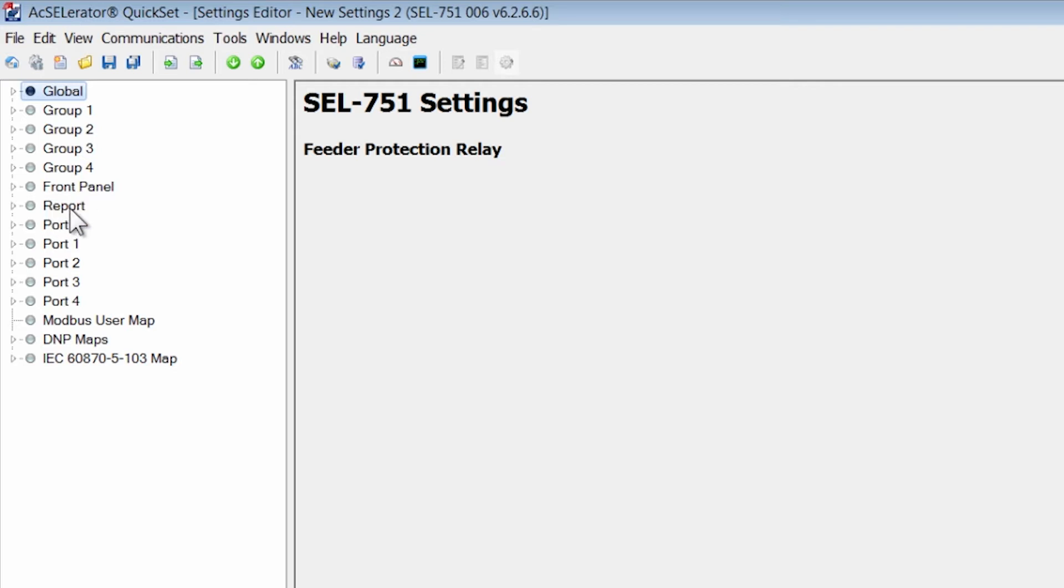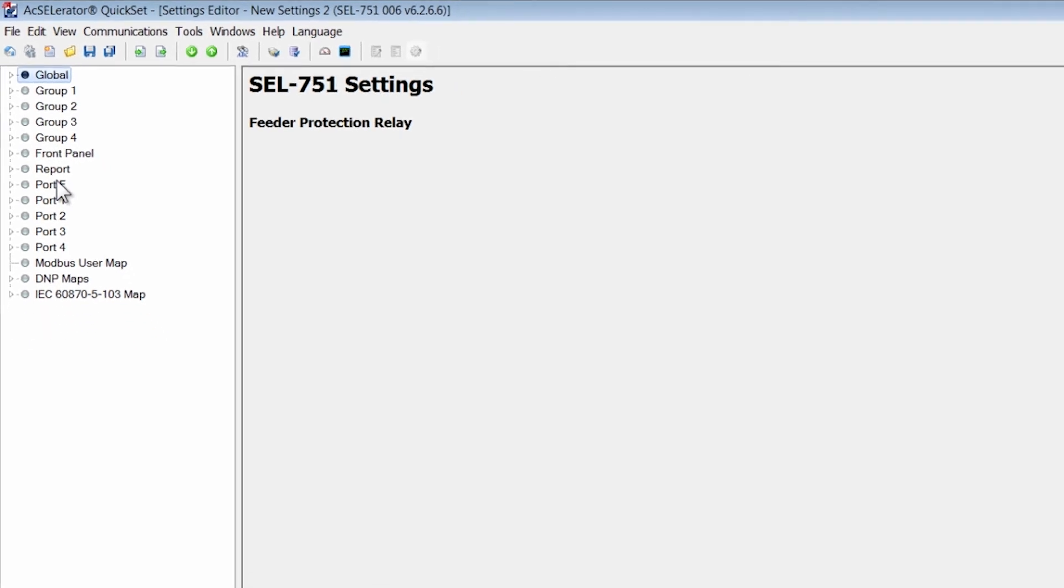The report section in the settings file is responsible for any event reporting capabilities such as triggering an event report without the relay tripping, logging SER data and programming which of the relay word bits are included in this. And below the report you have the various ports that are available on the 751 relay that can be configured.